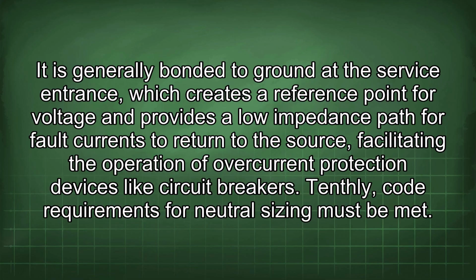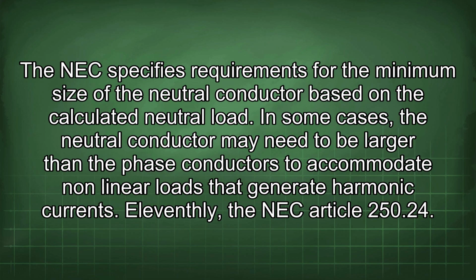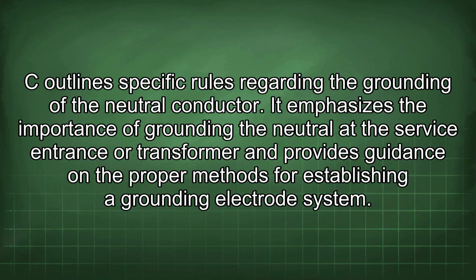Tenthly, code requirements for neutral sizing must be met. The NEC specifies requirements for the minimum size of the neutral conductor based on the calculated neutral load. In some cases, the neutral conductor may need to be larger than the phase conductors to accommodate nonlinear loads that generate harmonic currents. 11thly, the NEC Article 250.24(C) outlines specific rules regarding the grounding of the neutral conductor.